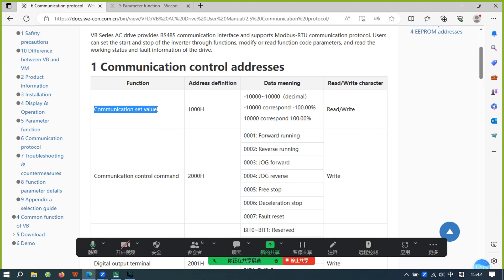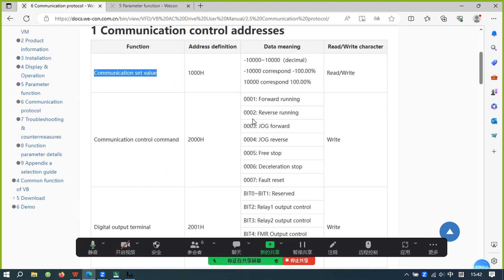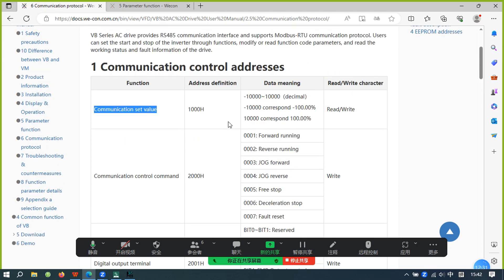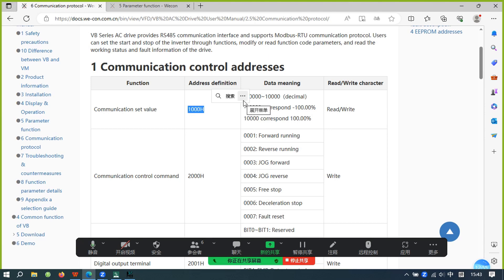The communication set value address controls the frequency of the inverter. When you add this address to an HMI project, you need to convert the HMI code to decimal. For example, the hexadecimal address in the manual is 1000H, which converts to decimal 4096. Set this value into the HMI for control.